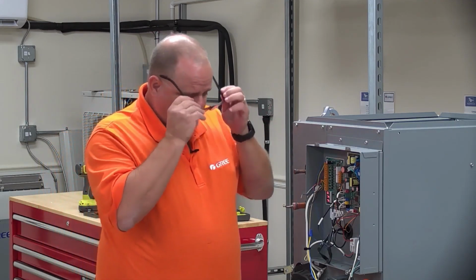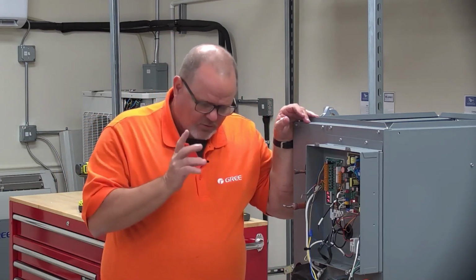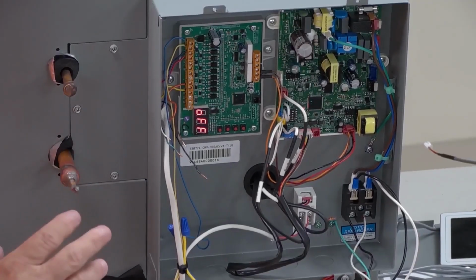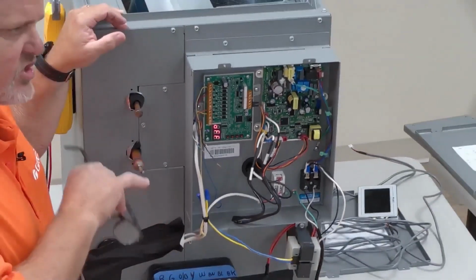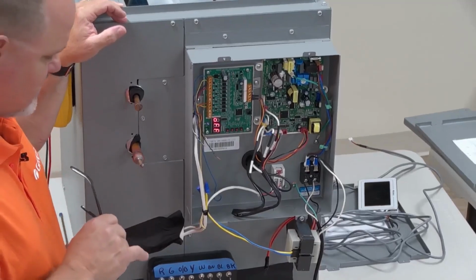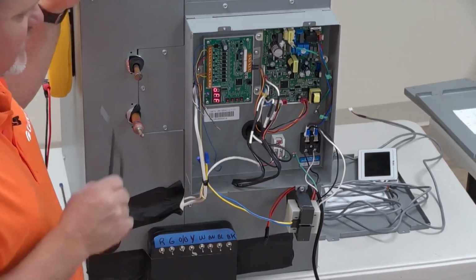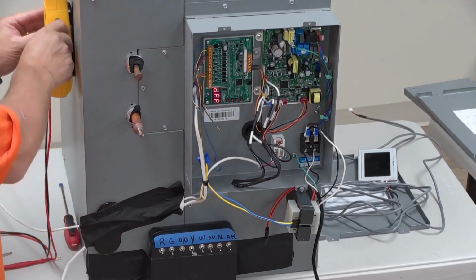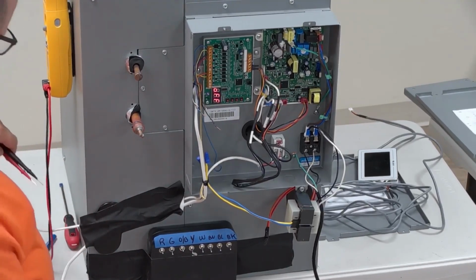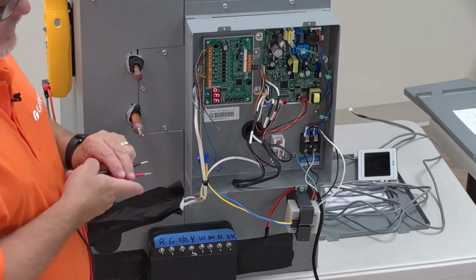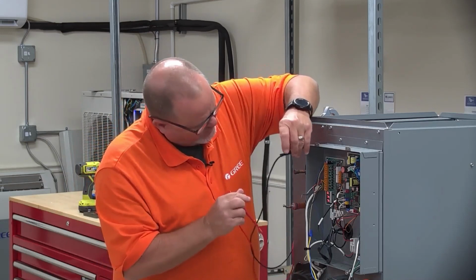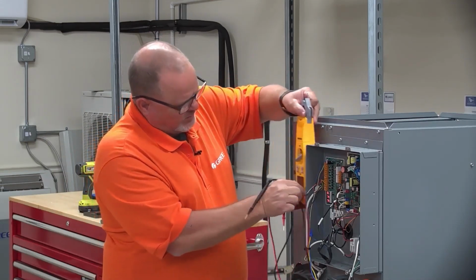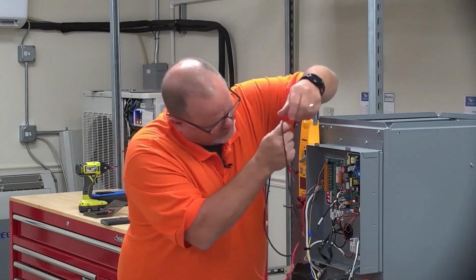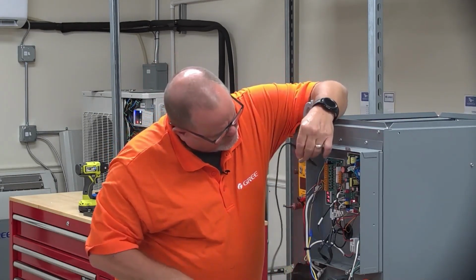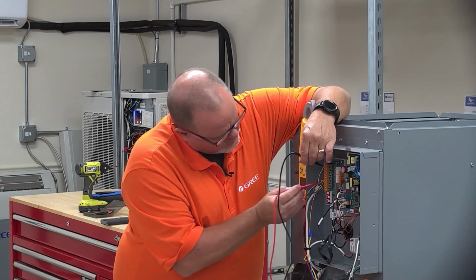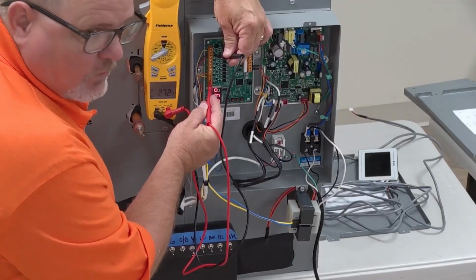So we'll kind of go through some of this. Your OB terminal, just like any other heat pump thermostat, when you switch that thing to heat, the system switch is what's energizing the reversing valve. So if I turn this switch on to energize the B terminal, that is no different than having the system switch on the heat pump on heat. So then if I pull this meter around here and go between C and B, you got 27 volts.